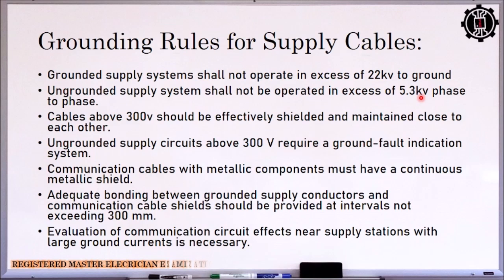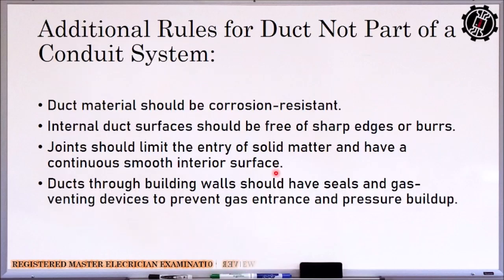Okay. So additional rules for duct not part of a conduit system. So duct material should be corrosion resistant. Our ducting must be corrosion resistant. It should be free from sharp objects or burrs, so that is to avoid damaging the insulation of our cable. It should limit entry of solid matter and have a continuous smooth interior surface. So during the installation, when underground, we have no cable tray, because a cable tray is open, so solid matter could enter there. That is why what is used is cable ducting. So ducts through building walls should have seals and gas venting devices to prevent gas entrance and pressure buildup.